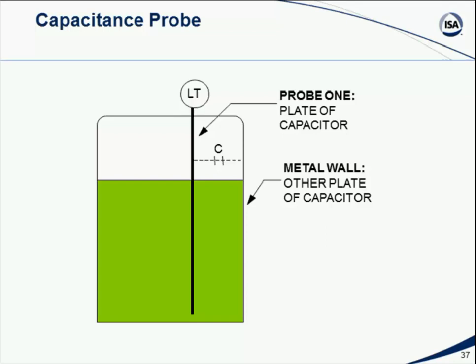Now, of course, if you have a non-metallic tank, it becomes a little more tricky. In that case, typically you insert two probes. If you have a fluid in the tank that is conductive, then what happens is you take your probe and you coat it with something, for example, totally coat it with a plastic and stick it down in. So again, you've got insulation. But in all of those different cases, there are solutions, and there are vendors out there that have the ability to pretty much deal with a wide range of different applications. And capacitive level measurement is a very well proven and commonly used technology.